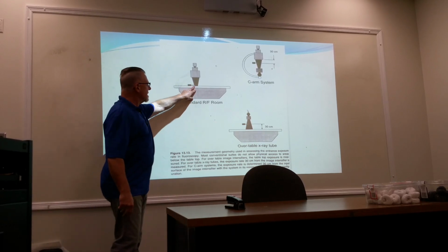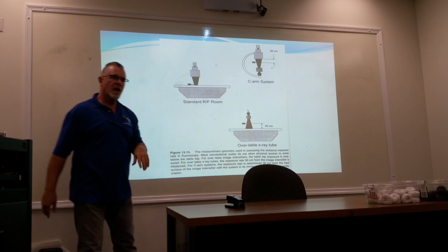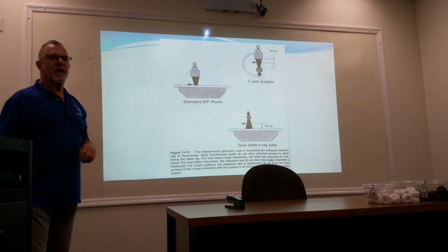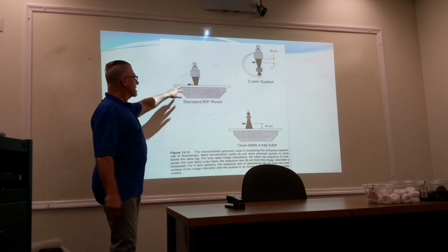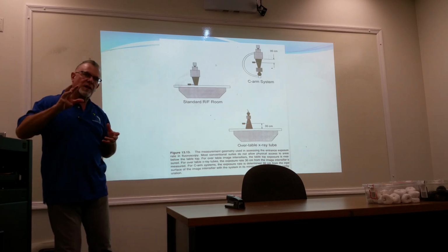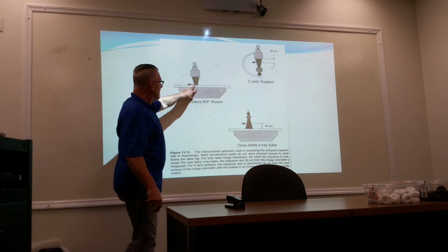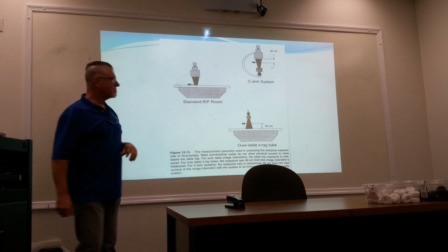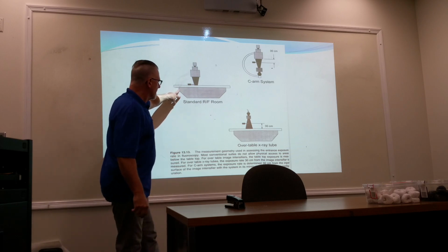It's only 2 centimeters between your chamber and the top of your table, but you still have to inverse square that back. And what's interesting is some engineers set that so close, if you inverse square 2 centimeters, you go out of compliance. Okay, so you do have to make sure you do that.